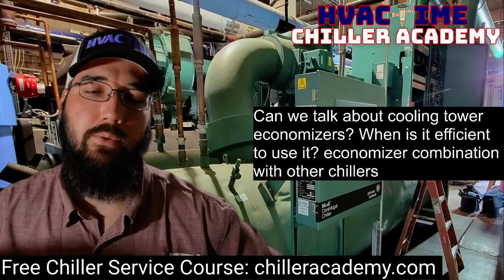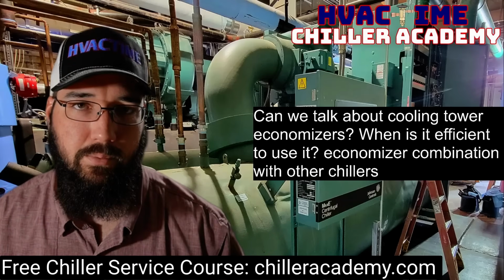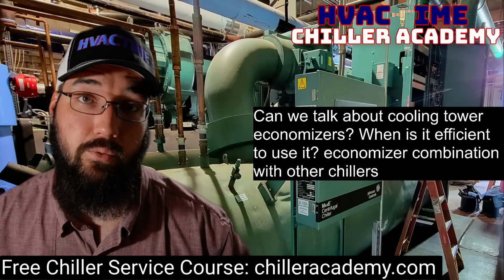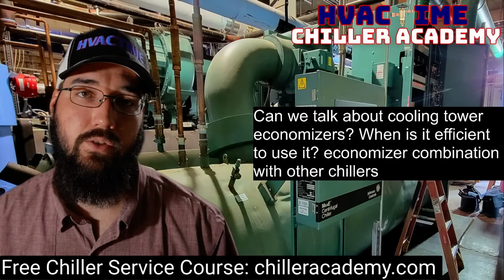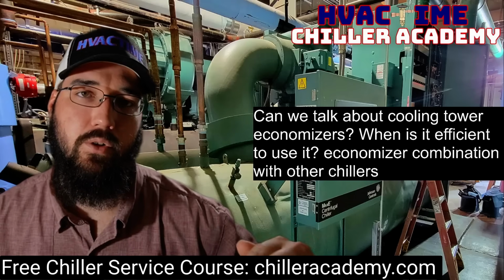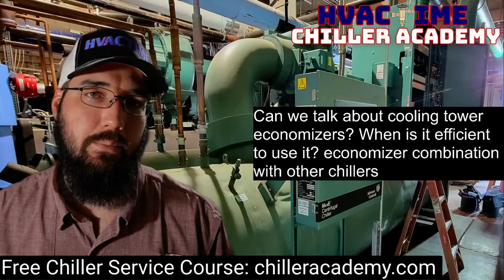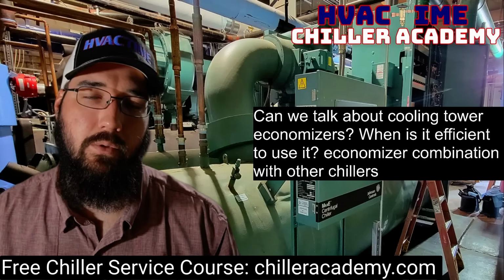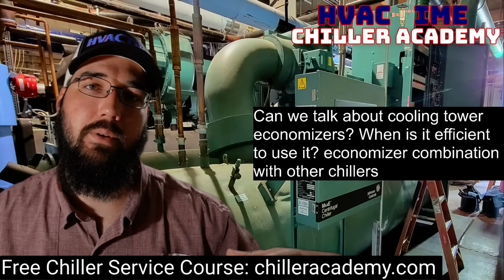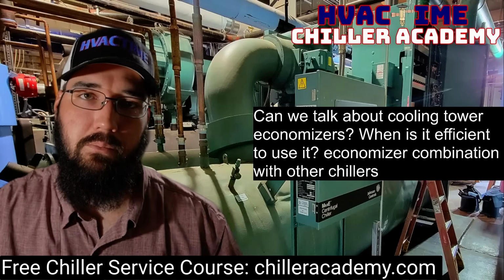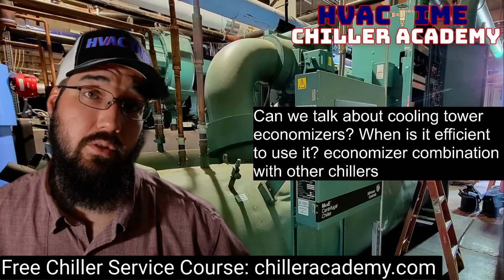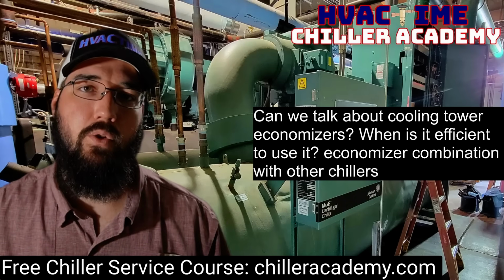So in the fact that we have a low enough wet bulb in the first place, we typically have a much lower humidity to begin with in this situation. Running a higher chill water temperature is not that big a deal because we're not worried as much about dehumidification. It's just about processing some general level of sensible load. That's really our only focus.